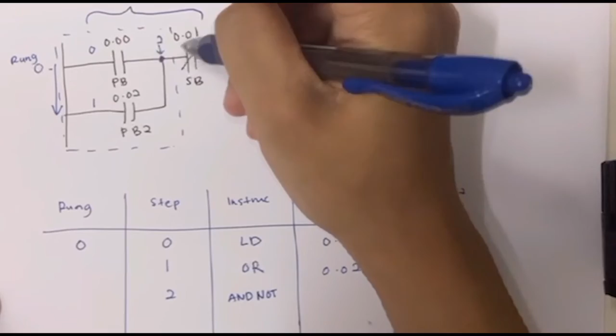Moving to the right, which is step number 2. Step number 2 is between PB and SB. It is in a series connection, so it must be known as AND. Since it is a normally closed contact, the instruction should be AND NOT, the operand is 0.01, and the comment is SB. The last one is the output, step number 3: the instruction is OUT, the operand is 100.00, and the comment is lamp. Settled for example 1, moving to the next example.